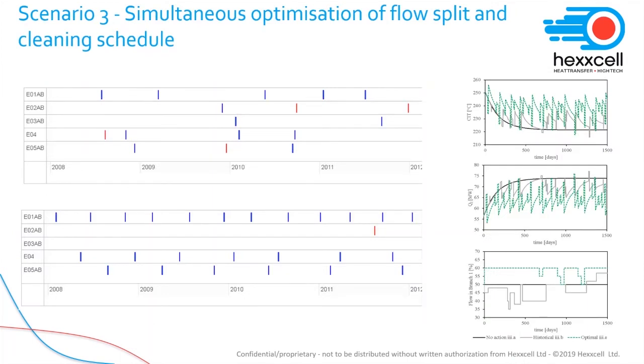If we now consider the simultaneous optimization of cleaning schedules and flow split operations, we can see how the flow split is adjusted based on the cleaning actions taken. While the heat exchanger is taken offline from one branch for cleaning, the flow split is adjusted in order to compensate for this change in the network. When the heat exchanger goes back online, the flow split is adjusted again.